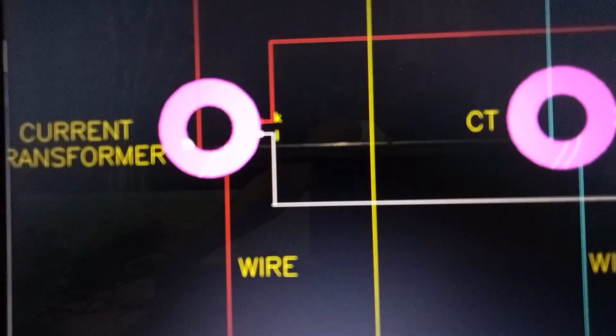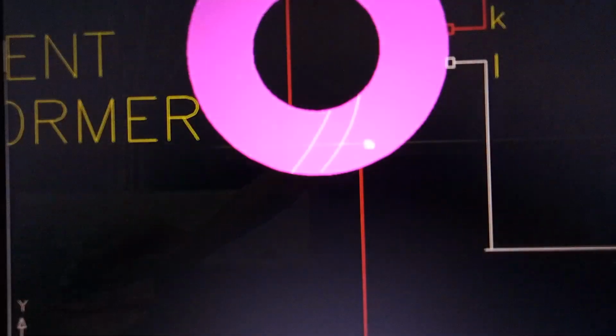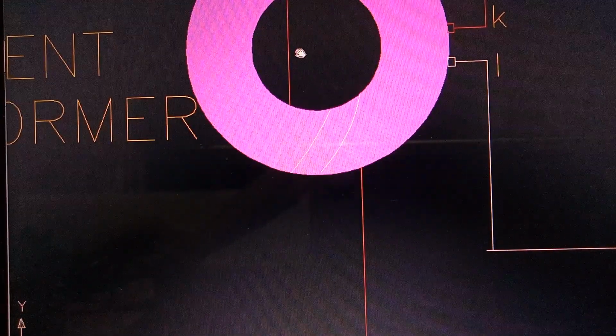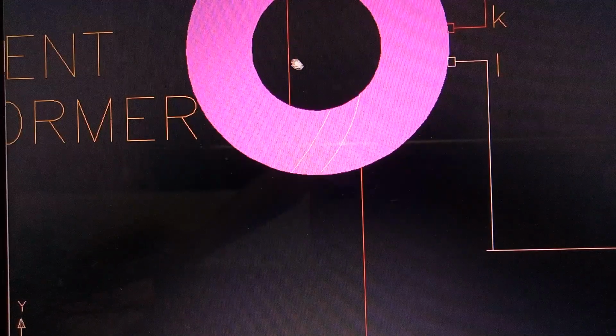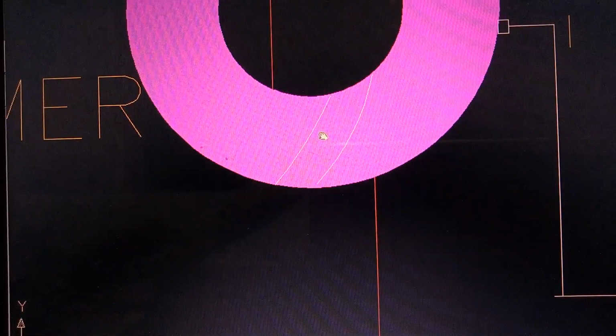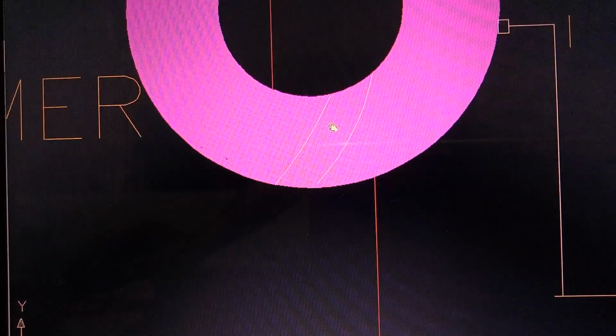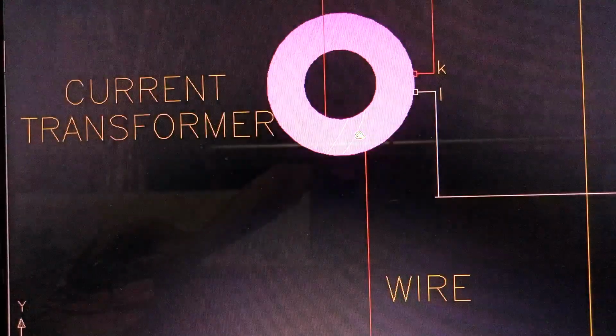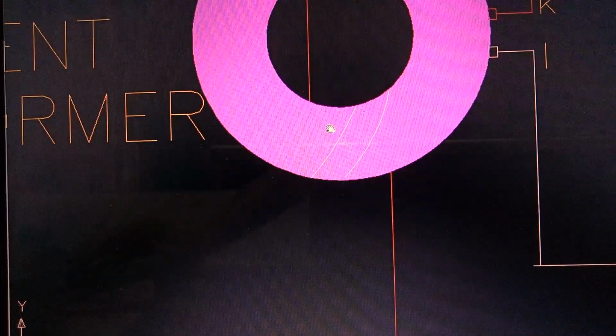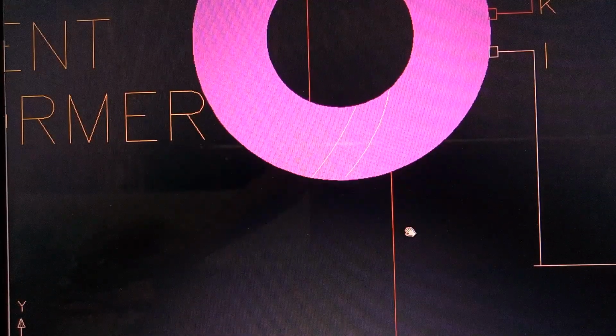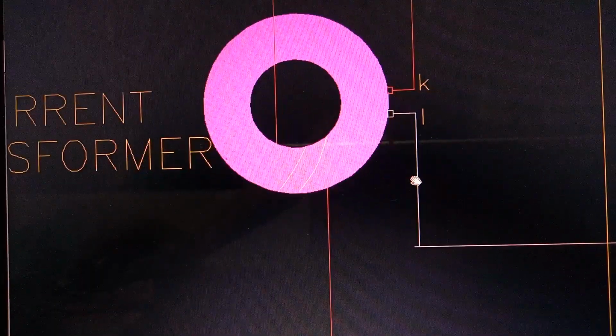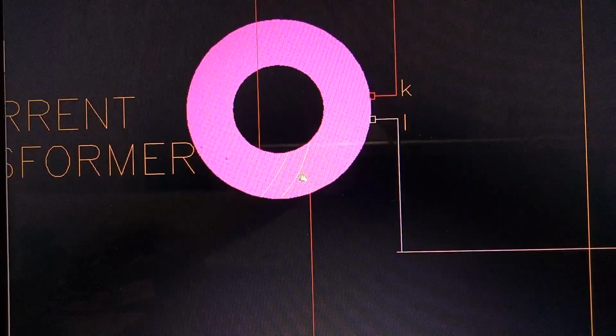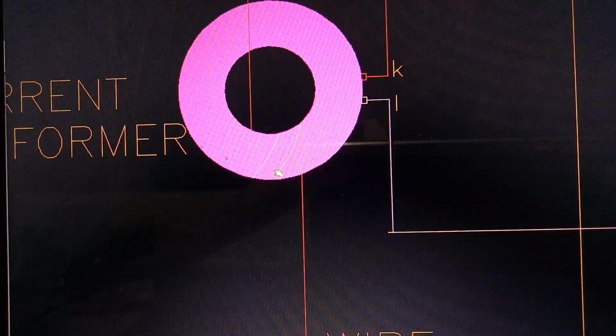In this third drawing, we still have two current transformers. One is on line 1, the other CT is on line 3. But now, instead of the wire going through the hole of the current transformer, the wire is wrapped 2 times on the side of the current transformer. There, it is wrapped 2 times before going to the load side, to the motor. So now the current will be increased because it is wrapped 2 times.